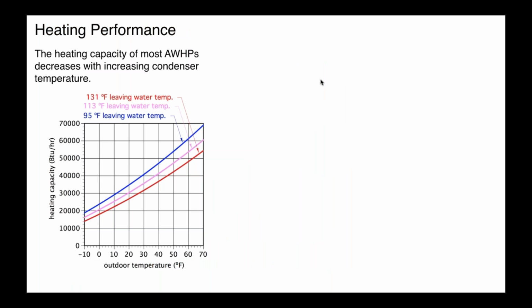Now, if you look at manufacturer's data, here's an example. What we're plotting here is outdoor temperature over a pretty wide range and heating capacity, BTUs per hour output of a particular heat pump. You'll see 3 curves here, and these are for 3 different what are called leaving water temperatures. This is the water temperature leaving the heat pump's condenser. And you can see the higher that temperature is, the lower the heating capacity for any given outdoor condition.